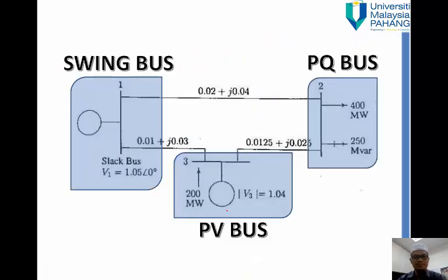This is an example for the slack bus: we know V and the magnitude as well as the angle, normally referred to as zero. In the PQ bus, we know P in megawatts and Q in MVAR. In the PV bus, we know the P generation, 200 megawatts, and the magnitude 1.04, so the unknowns are QG and the angle. For the PQ bus, we want to find voltage and angle; for the swing bus, we want to find PG and QG.